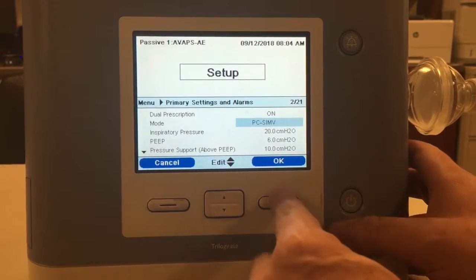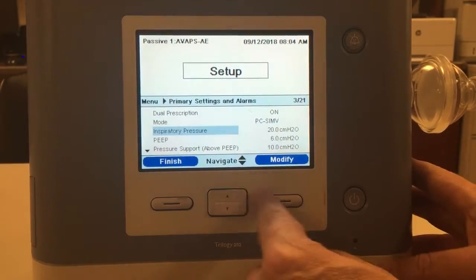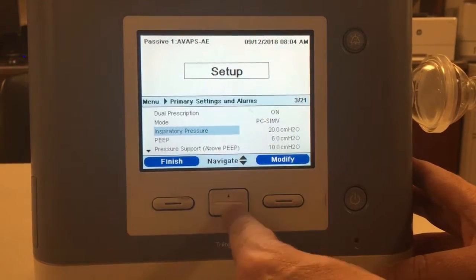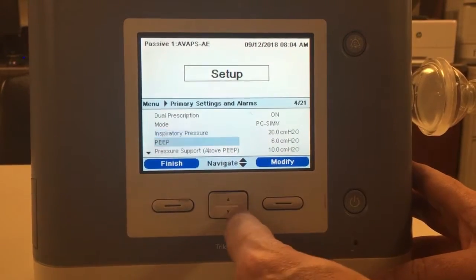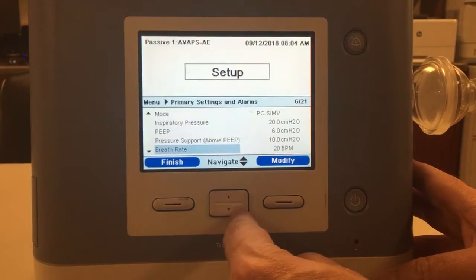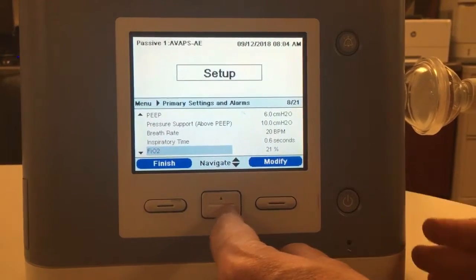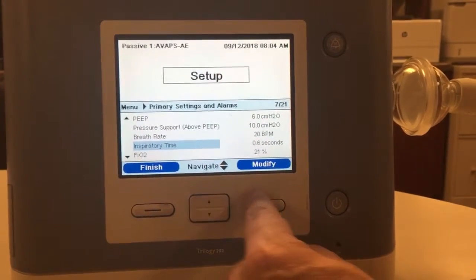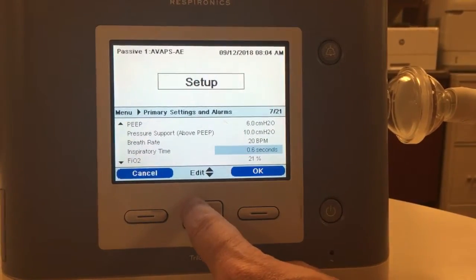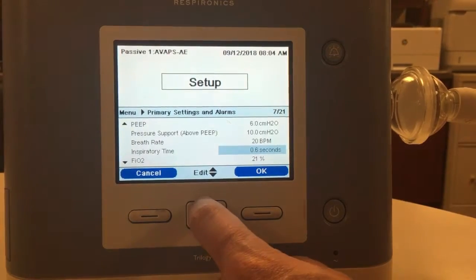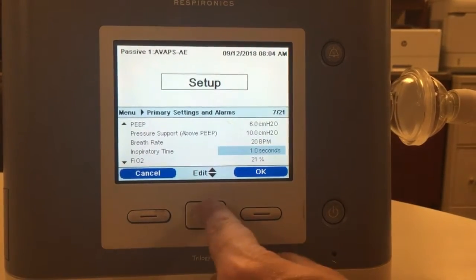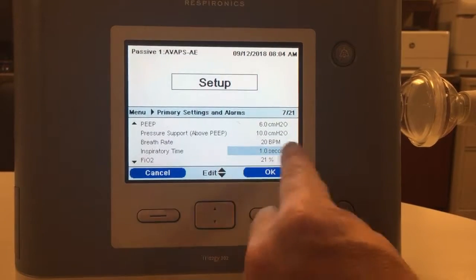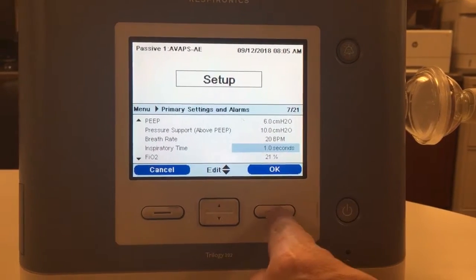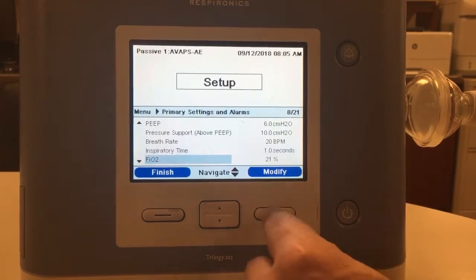Let's say, for instance, here we'd like to do pressure control SIMV. We would just hit yes. And now it's on here, and now you'll scroll through your different settings: inspiratory pressure, 20, your PEEP, pressure support above PEEP, and so on, breath rate, inspiratory time. And to change any of these features, you could just go to inspiratory time. The patient needs a little longer inspiratory time. You just go ahead and highlight it. As you can see, once it's highlighted with the box, you can change it with the up and down arrows. Then to set it, just hit OK.